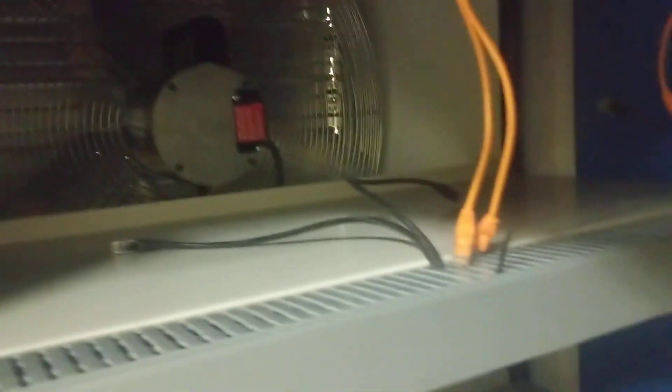This is a steel rack that'll house all your ASICs. In the Panduit, that's where you feed the power cables, and all the ethernet cables are pre-wired. There's a network switch up on top for each rack — every rack has its own network switch. Every rack is also paired with a half-horsepower exhaust fan.